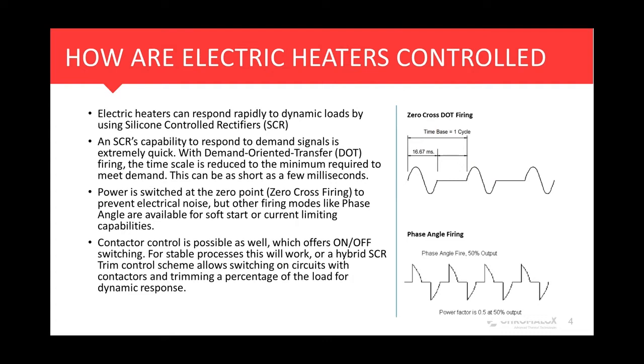This works basically by shrinking down the time scale for how often that SCR is conducting and not conducting, to be as accurate as possible. So you can see, just as an example on the right, a 50% load would actually shrink the timescale down to where you're on for about 17 milliseconds, off for 17 milliseconds. That's a very, very quick and rapid firing that allows you to respond to dynamic loads and really keep up with your process very accurately.